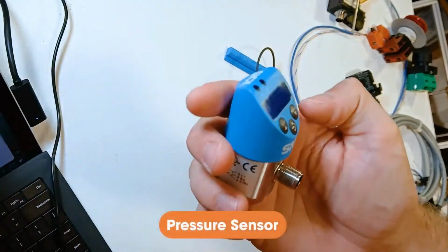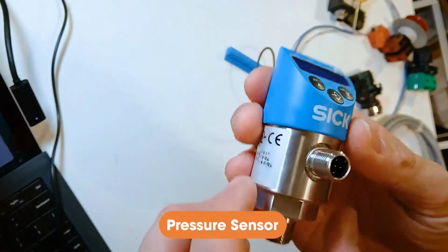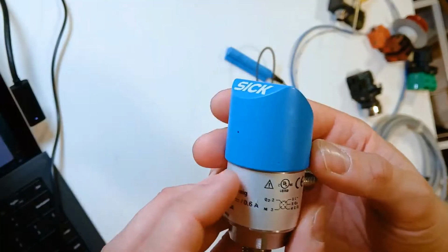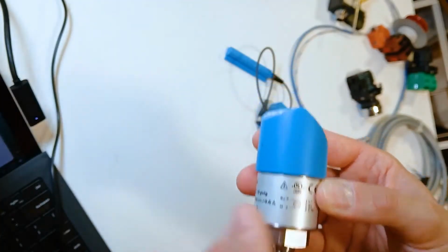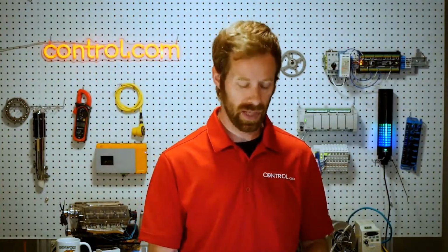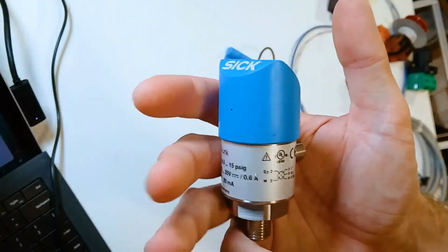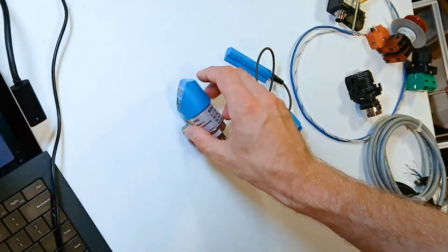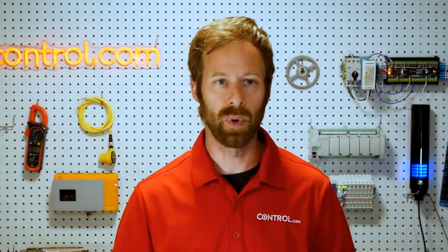I also have a pressure sensor. This pressure sensor has a minimum and maximum, but it also has all of the previously discussed data: different set points, the analog value, being able to set parameters, being able to read the previously set parameters between the device and the control system, giving us a much more flexible system. It is more flexible, but that also means, and usually means, that it is a bit more complicated. So what do we need for an I/O link system?